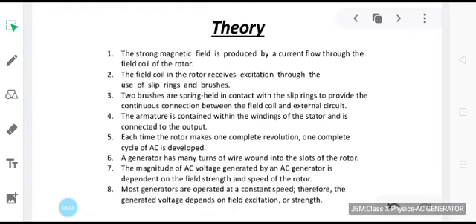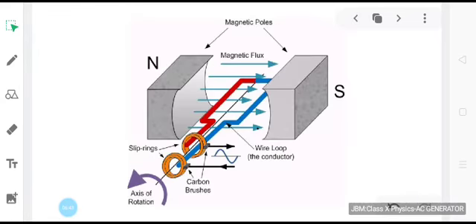Now we will begin with the working principle. The strong magnetic field is produced by a current flow through the field coil of the rotor. The field coil in the rotor receives excitation through the use of slip rings and brushes. Two brushes are spring-held in contact with the slip rings to provide a continuous connection between the field coil and the external circuit. The armature is contained within the windings of the stator and is connected to the output. Each time the rotor makes one complete revolution, one complete cycle of AC is developed.